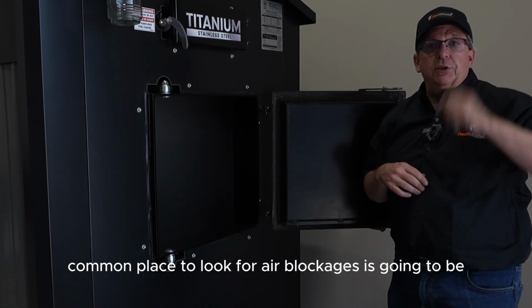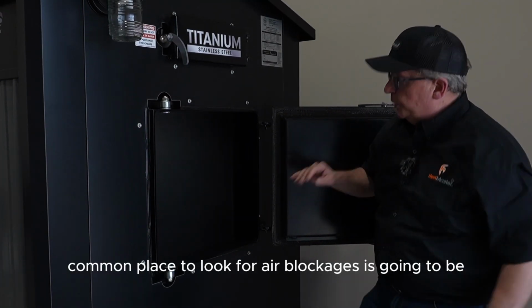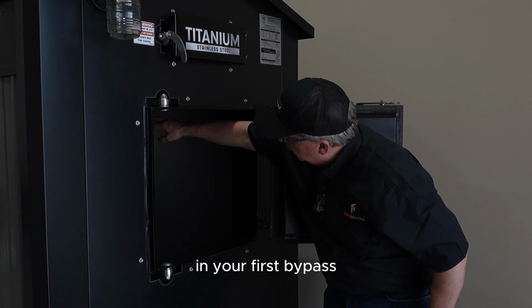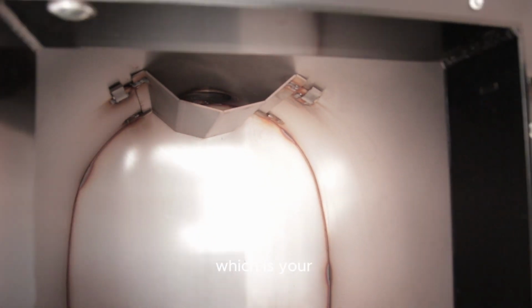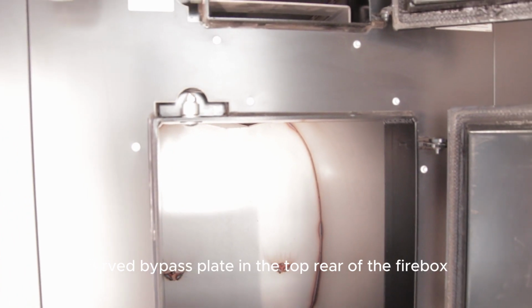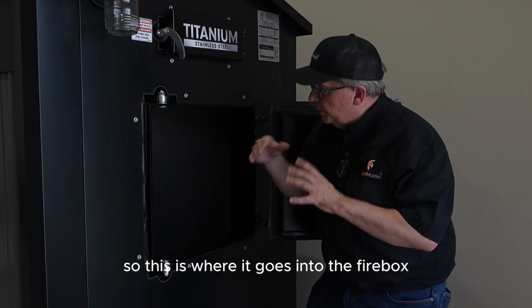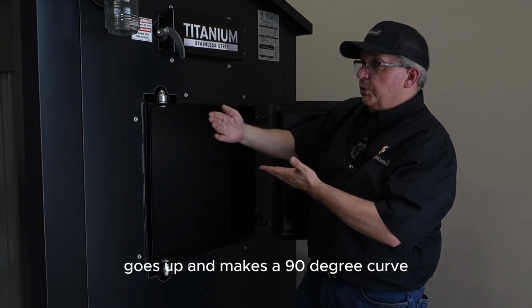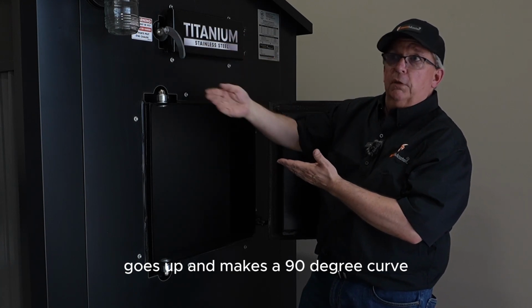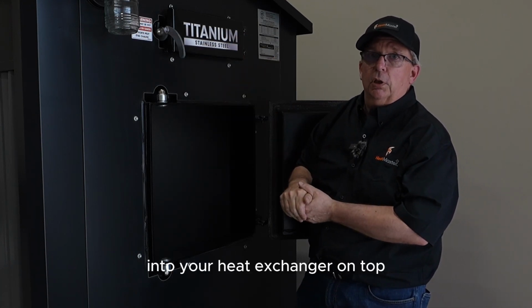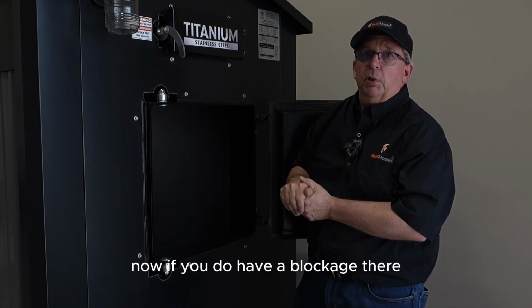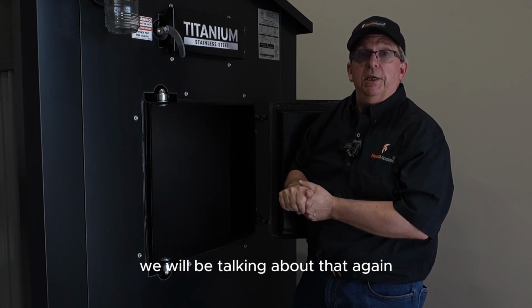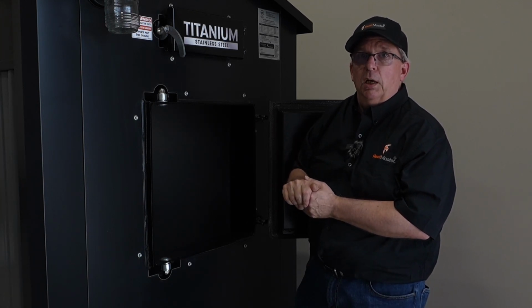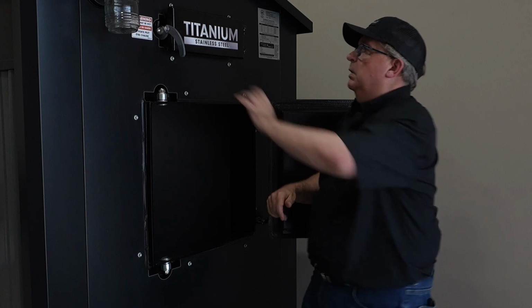The next common place to look for air blockages is going to be in your first bypass, which is your curved bypass plate in the top rear of the firebox. This is where it goes into the firebox, goes up, and makes a 90-degree curve into your heat exchanger on top. Now, if you do have a blockage there, we will be talking about that again in the maintenance video that's coming up in the program.